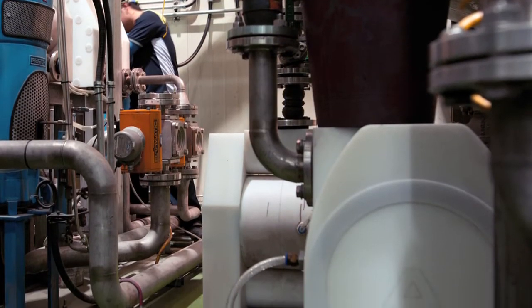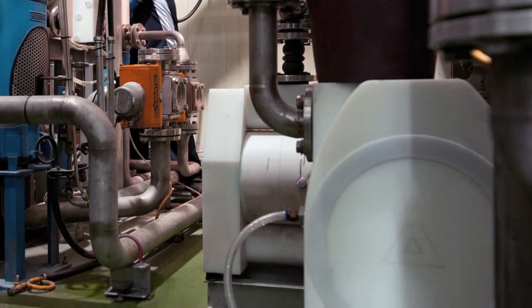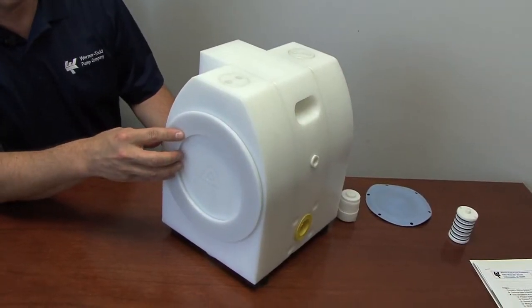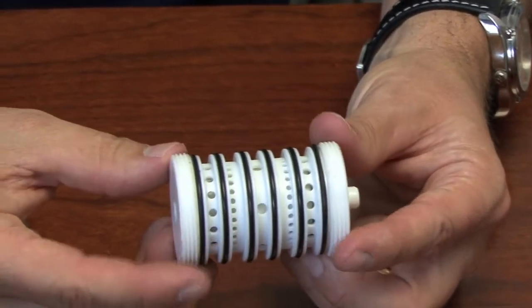The abrasive nature of this slurry doesn't lend itself well to conventional pumps. That's where the E-series design plays a big part for them. With the previous metal pump design, they were getting anywhere from two to three months' life, at the very most sometimes five months. With the Almatec design and the polyethylene plastic material, they're getting dramatically longer life out of their pump.